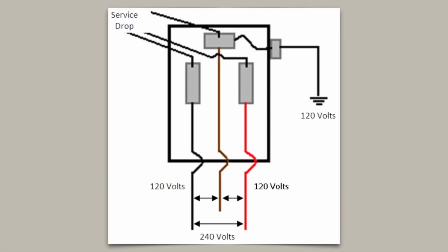Service drop, above ground service. The service drop is the wire running from the weatherhead to the electric meter. This wire must be securely and safely attached to the house as it runs to the meter. It should be checked for deterioration and fraying. The insulation sometimes becomes so worn that the bare cables are exposed. The service drop should be properly sealed at the entrance to the meter to prevent water infiltration. Sometimes the service drop is housed in a metal conduit and is not visible.